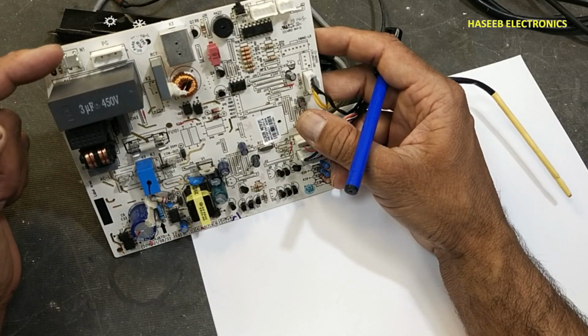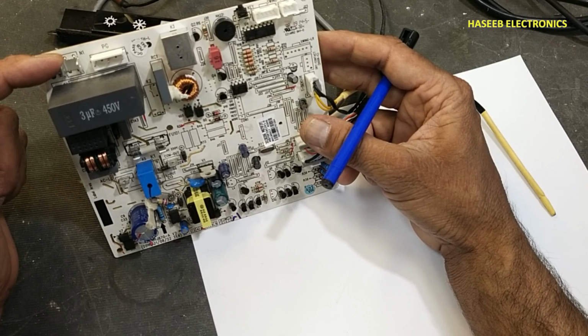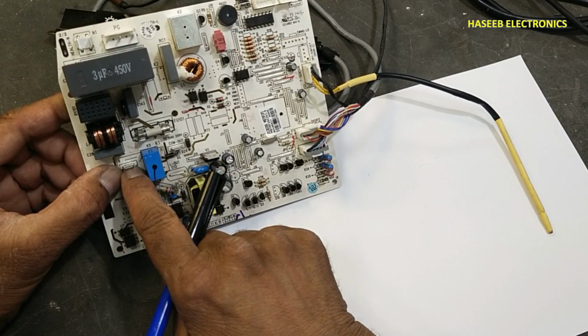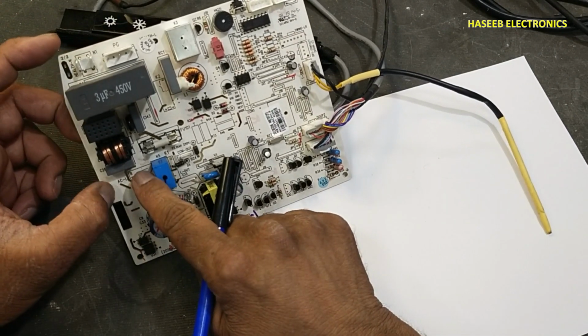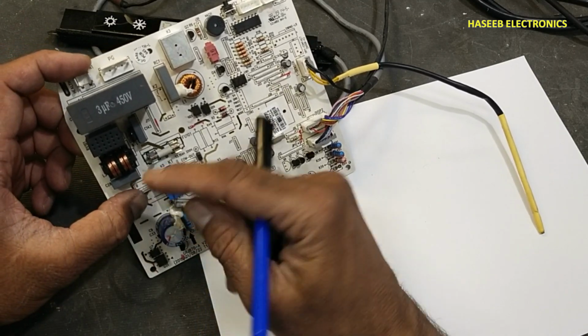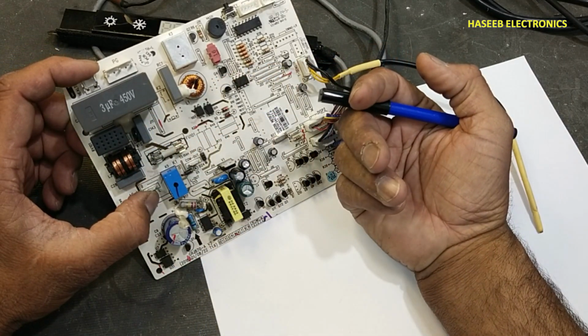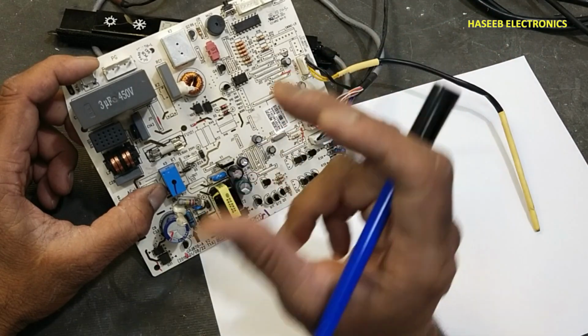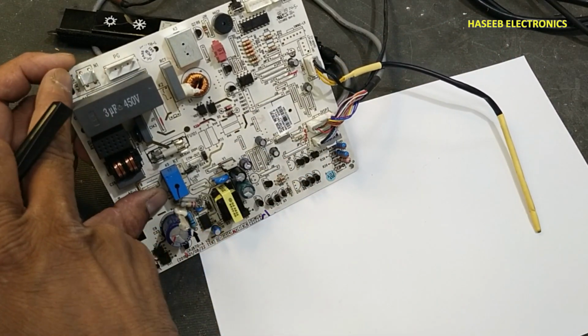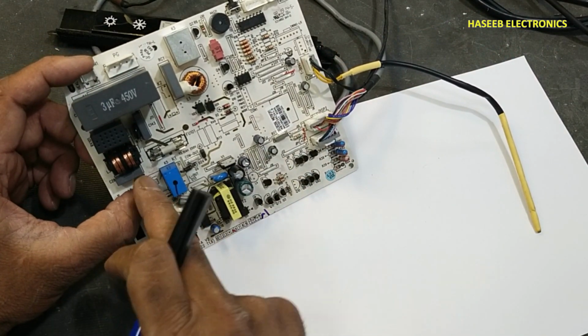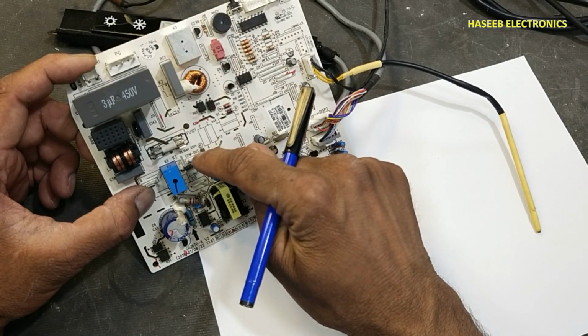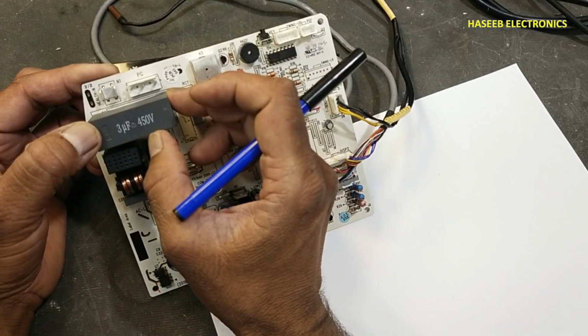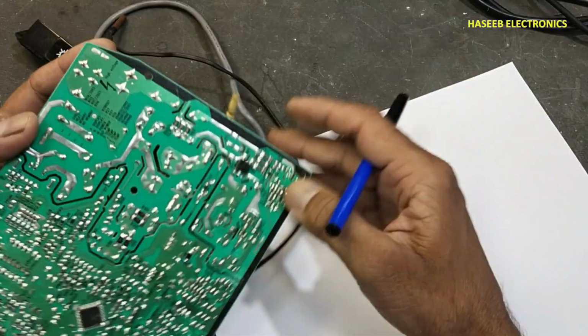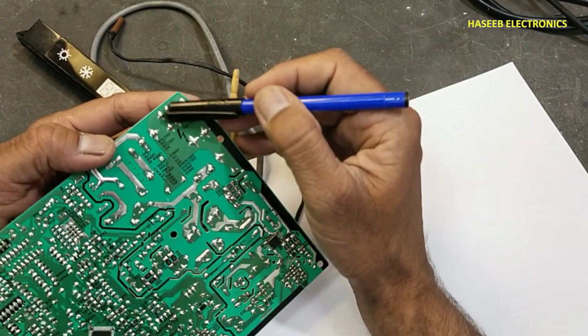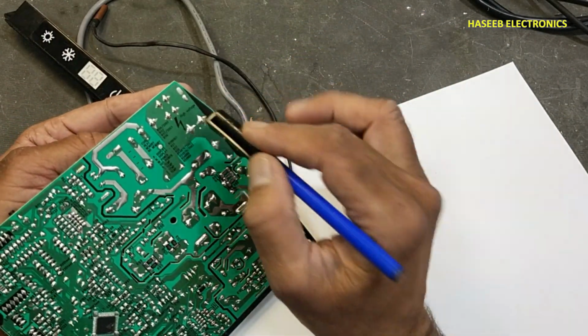Here we have the neutral connection. Here is the line connection, phase and neutral. Two connections are coming from the outdoor unit. Main power is supplied to the outdoor unit, and from there these two wires are coming here. The third wire is the communication wire. This capacitor is for the fan motor. Neutral is applied here. It is connected to this fan capacitor.